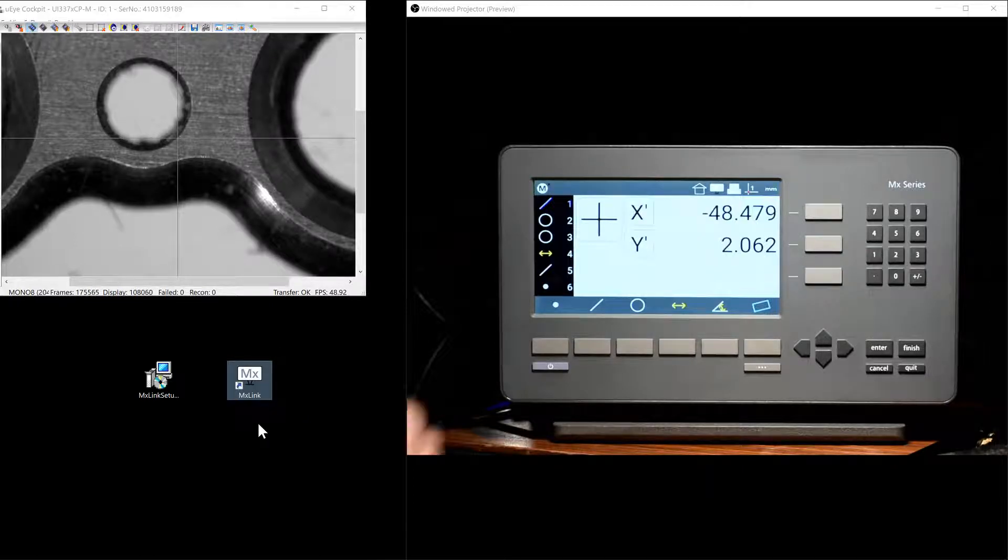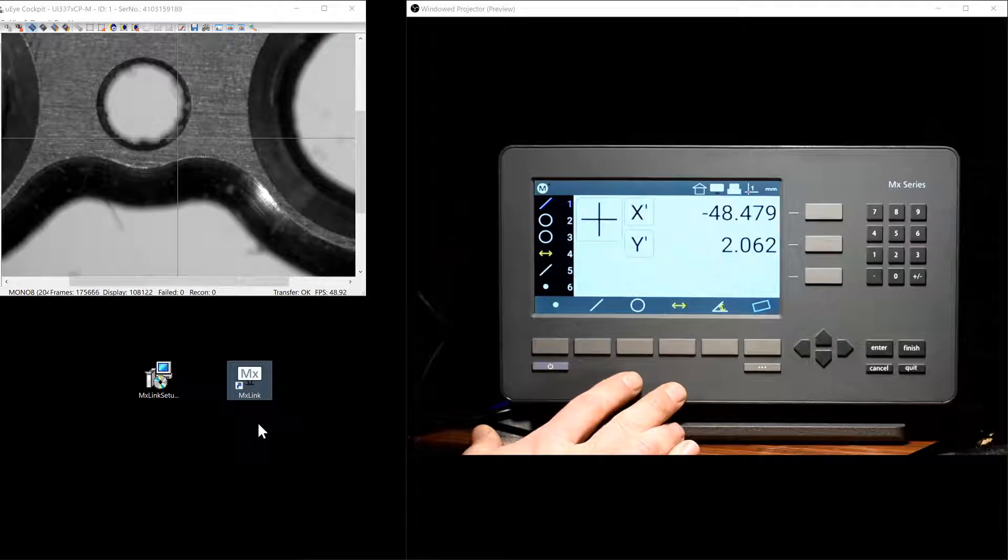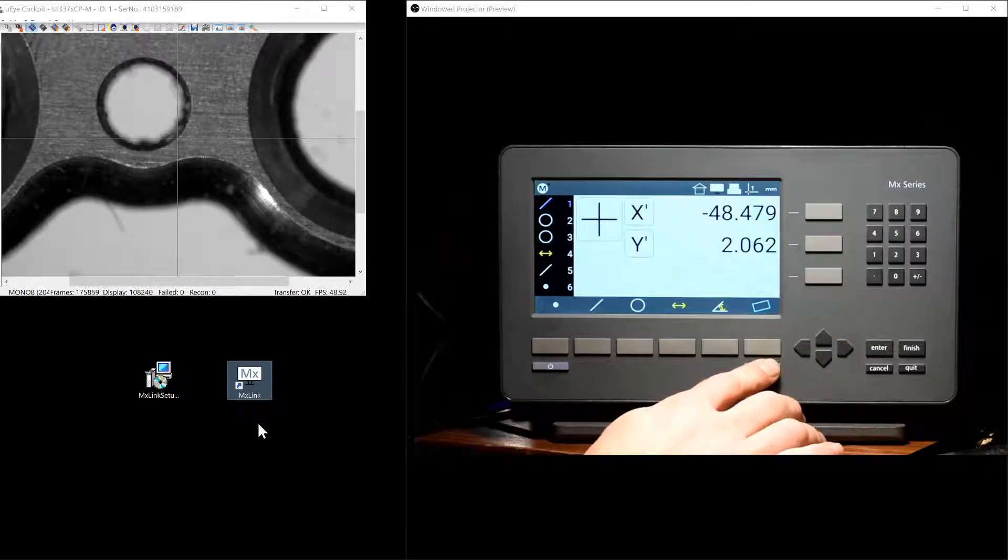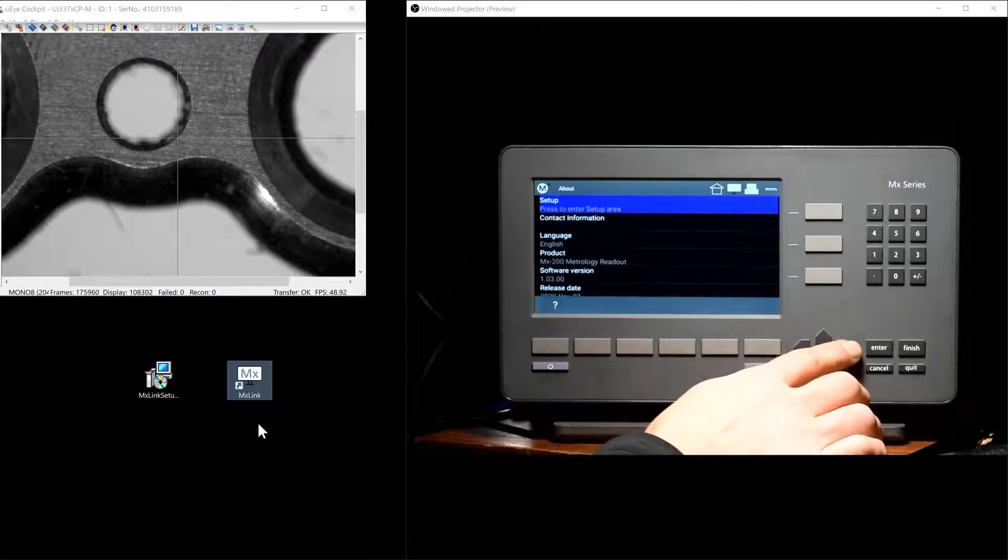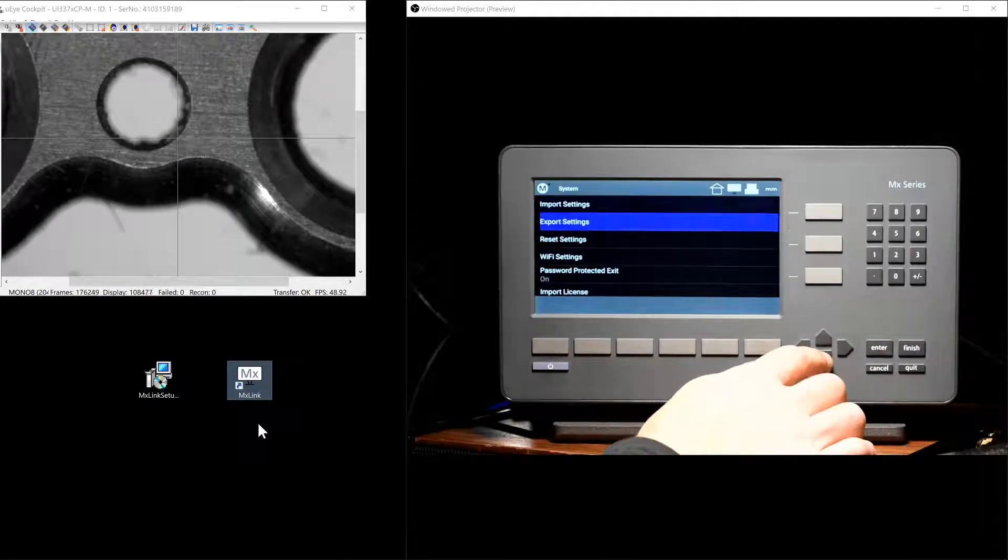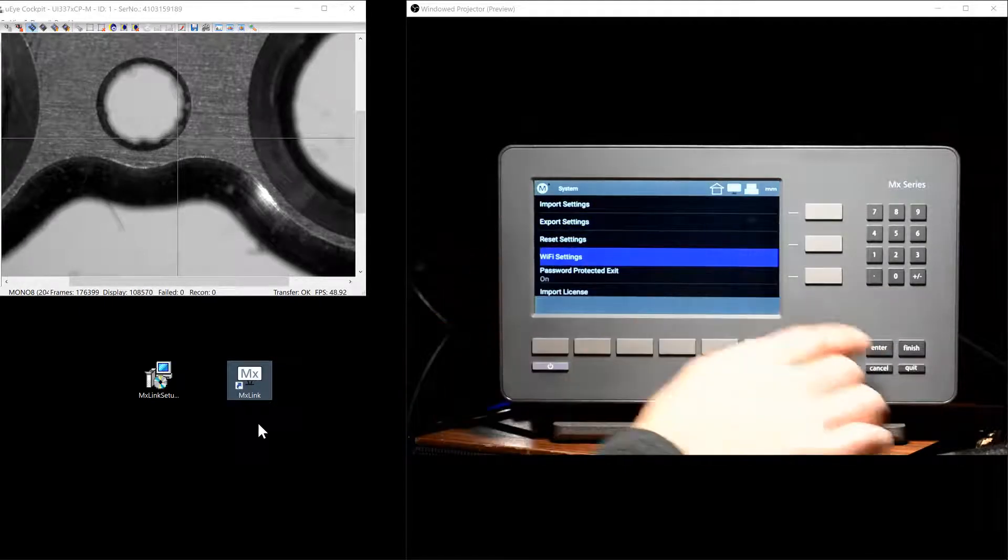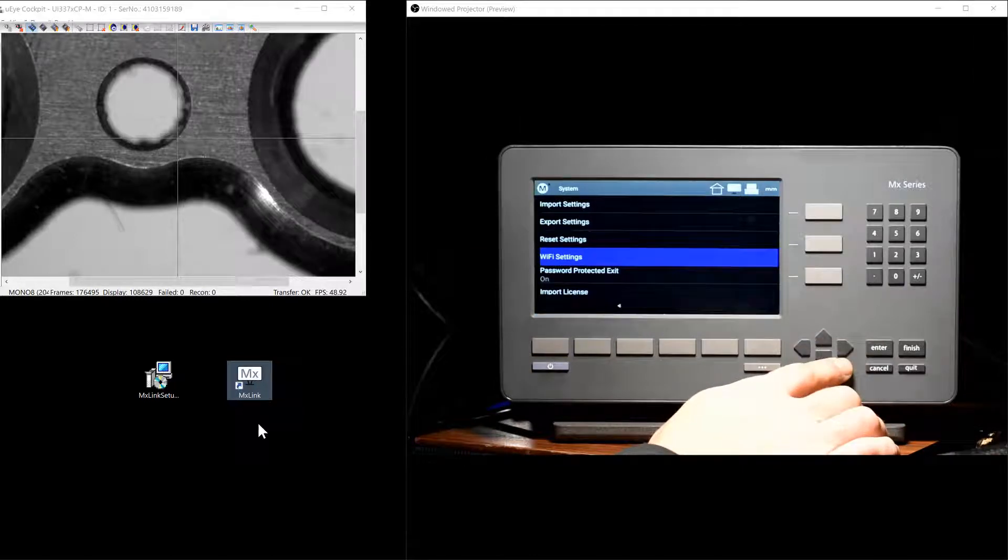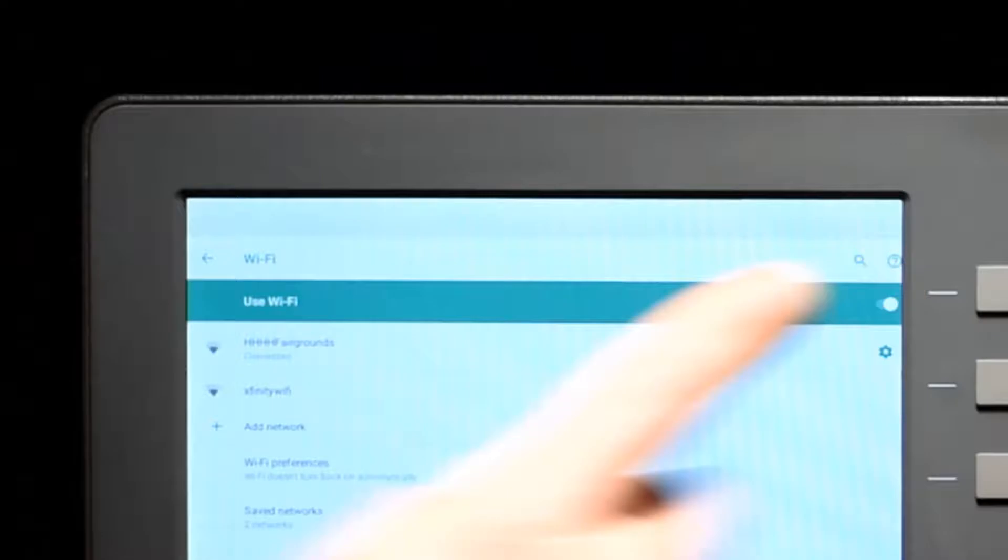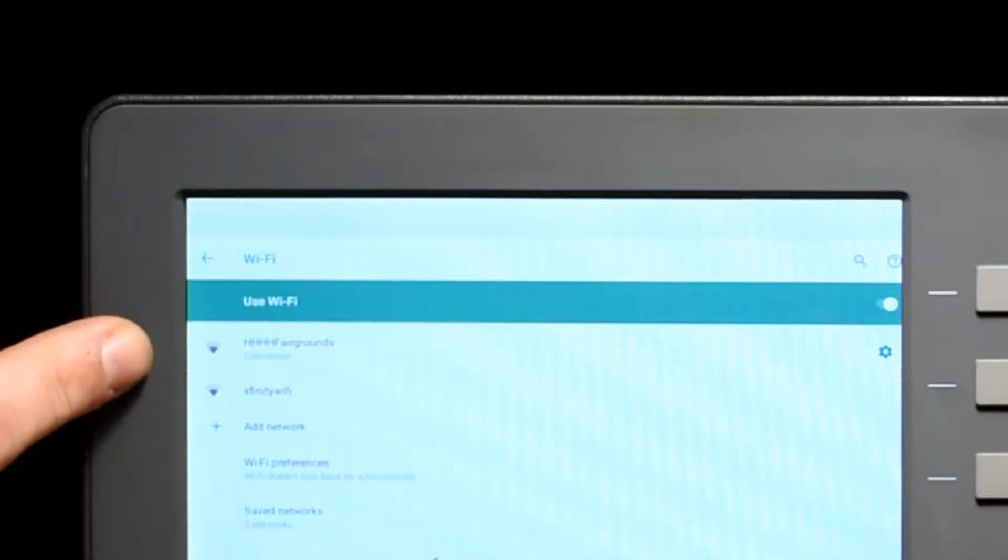Next, we need to ensure that our readout is successfully connected to a network. We're going to go ahead into the MX Setup menu, into Setup, and into the System menu in order to access the Wi-Fi settings screen in the MX200 readout. As you can see, the Wi-Fi radio is enabled and we've successfully communicated with a network.